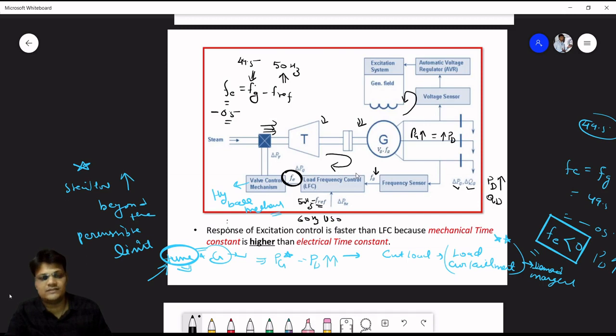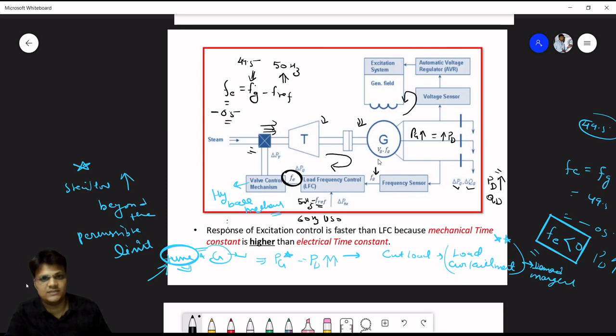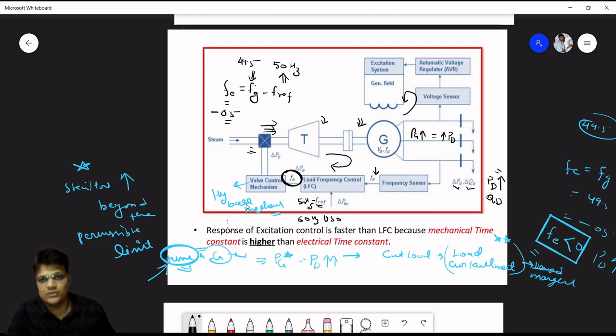This is called load frequency control because it depends on the variation of loads. When the load changes, frequency changes accordingly, the governor system operates, the valve opens or closes, and the turbine steam flow rate increases or decreases to match generation to demand. However, we cannot increase the flow rate beyond the permissible limit of the turbine and generator.